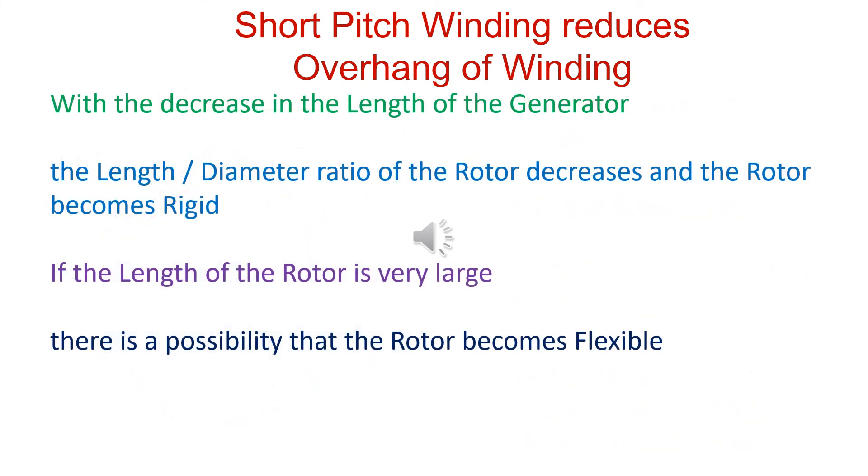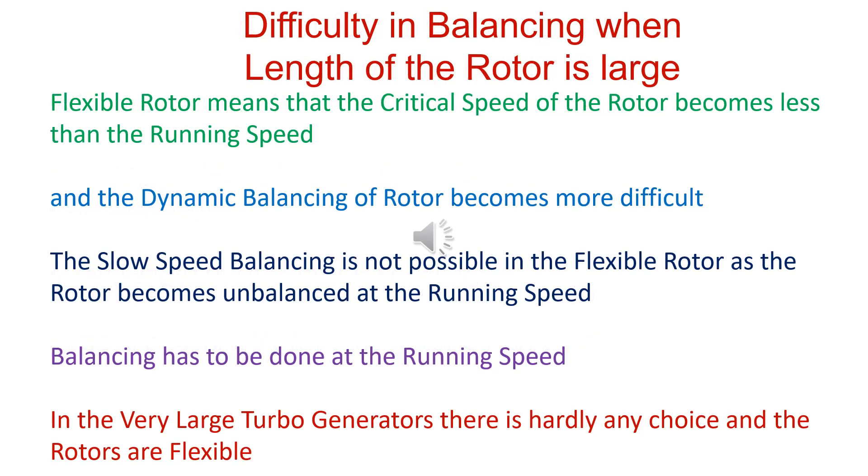Length by diameter ratio of the rotor is reduced. If the length of the rotor is very large, the rotor may become flexible. Critical speed, especially in two-pole machines, may become less than running speed, and dynamic balancing becomes difficult.